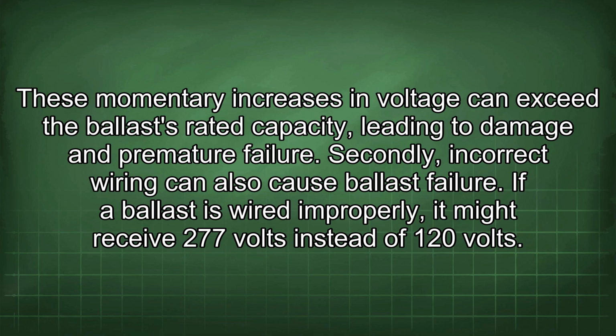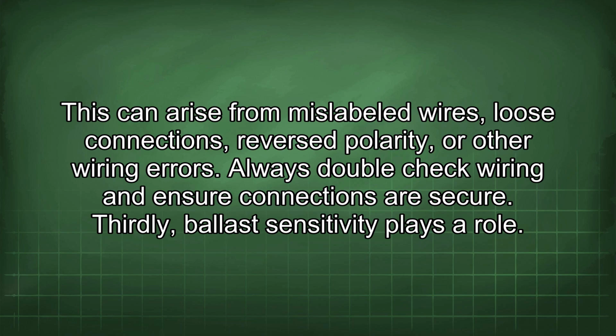Secondly, incorrect wiring can also cause ballast failure. If a ballast is wired improperly, it might receive 277 volts instead of 120 volts. This can arise from mislabeled wires, loose connections, reverse polarity, or other wiring errors. Always double-check wiring and ensure connections are secure.